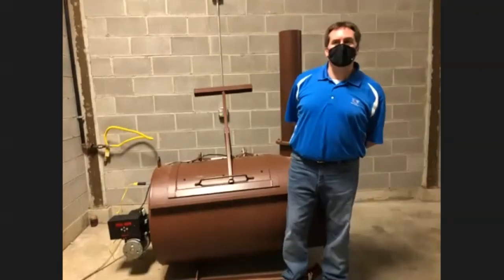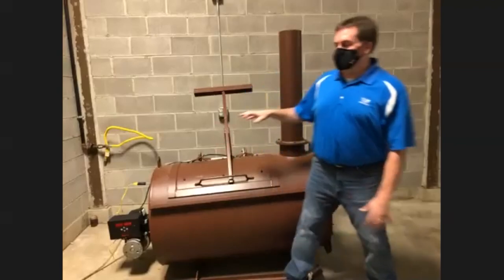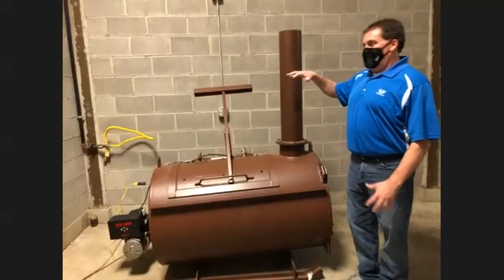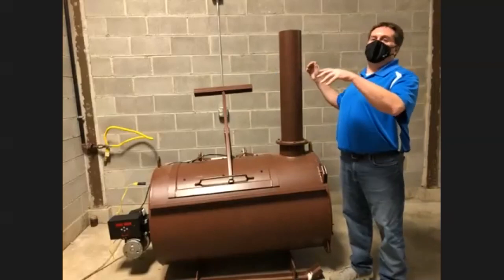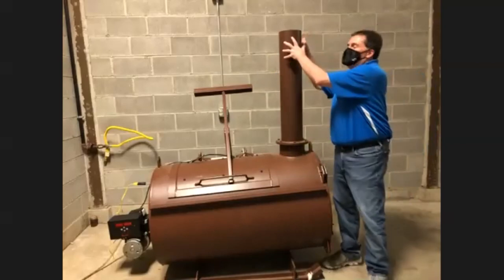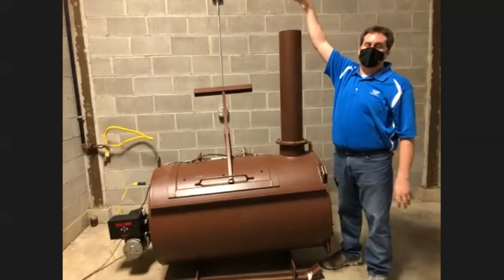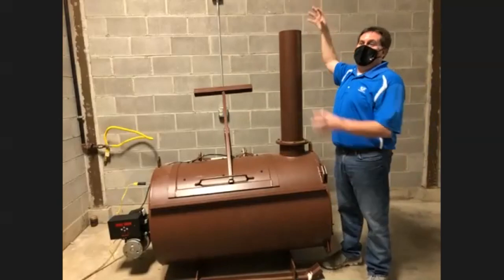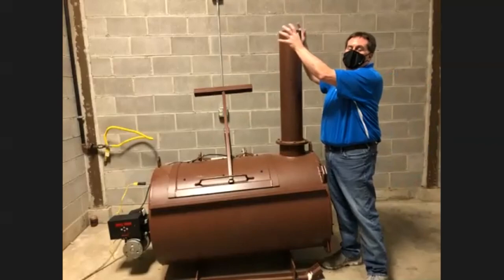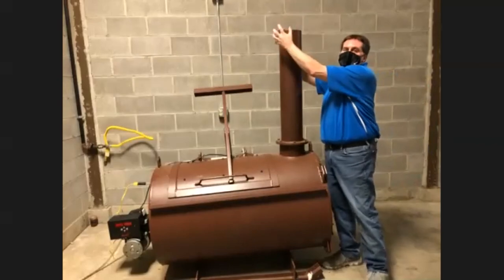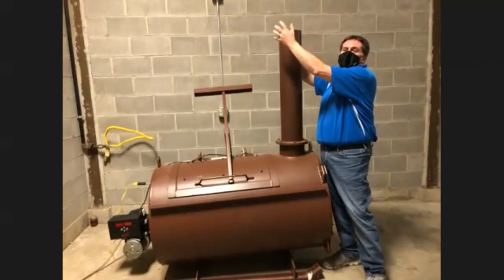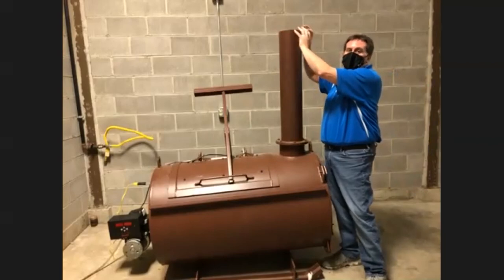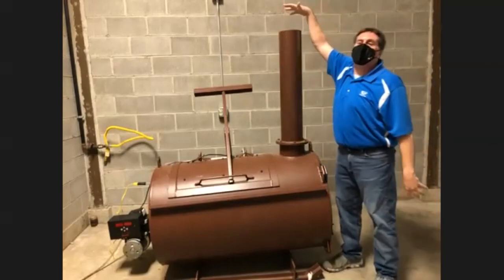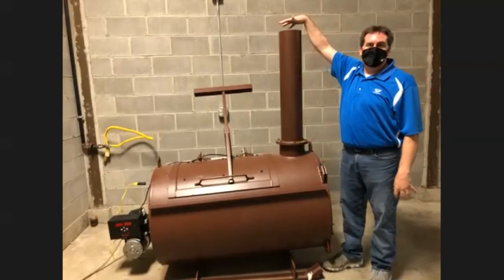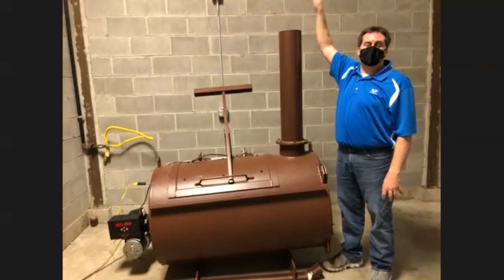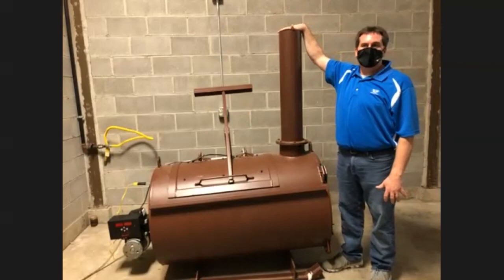Oh yes. We never typically want a roof over these. If you do install a cover over these, like a carport cover, you must make sure the exhaust stack goes through that roof and extends 2 to 3 feet. And if you're going through a type of shelter or covering, it has to have proper heated ductwork around it to protect itself. Again, follow proper codes. But you typically do not want to cover these up because it'll change the exhaust flow and it may not burn very efficiently at all.